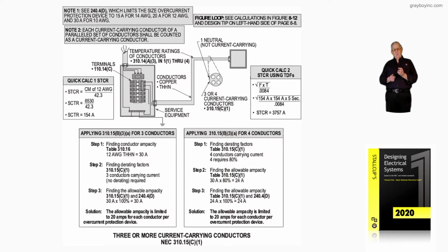So we can derate from that 90 degree column as permitted in 110.14C, as well, very well explained in 334.80 of the NEC. So after the correction factors of 76% have been applied, that number 8 conductor is only good for 41.8 amp.